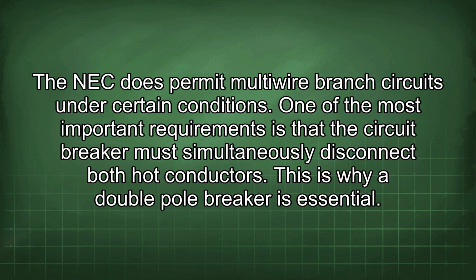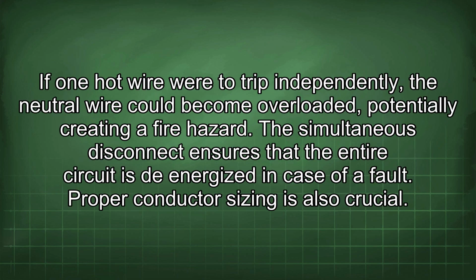The NEC does permit multi-wire branch circuits under certain conditions. One of the most important requirements is that the circuit breaker must simultaneously disconnect both hot conductors. This is why a double pole breaker is essential. If one hot wire were to trip independently, the neutral wire could become overloaded, potentially creating a fire hazard. The simultaneous disconnect ensures that the entire circuit is de-energized in case of a fault.